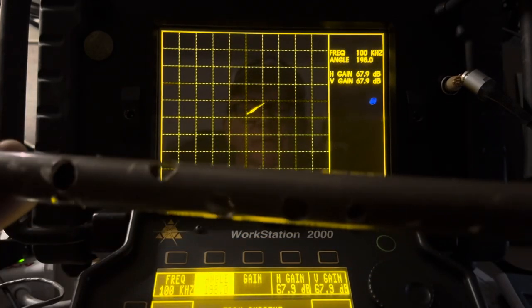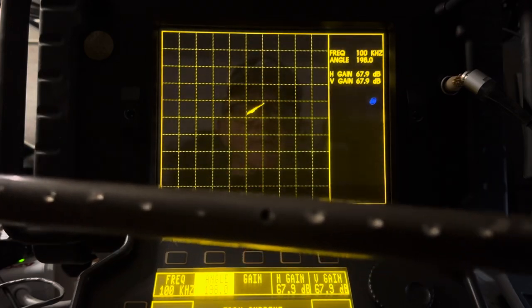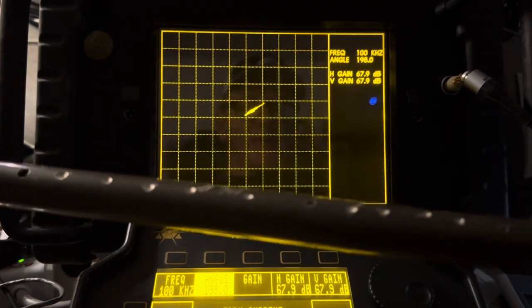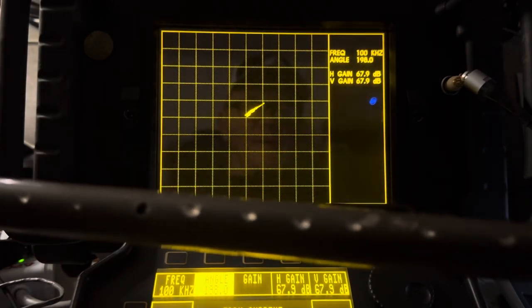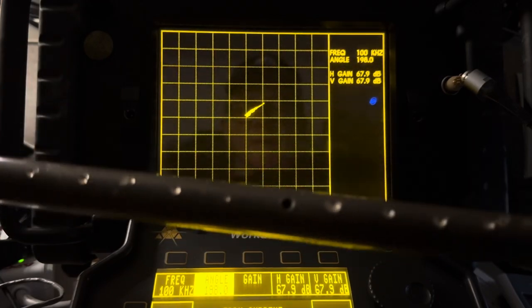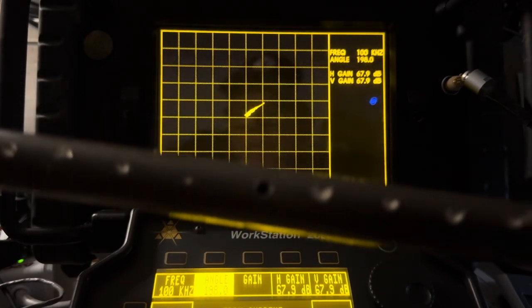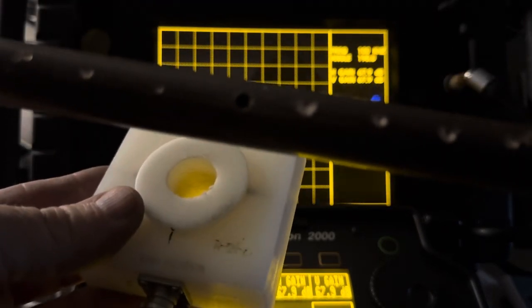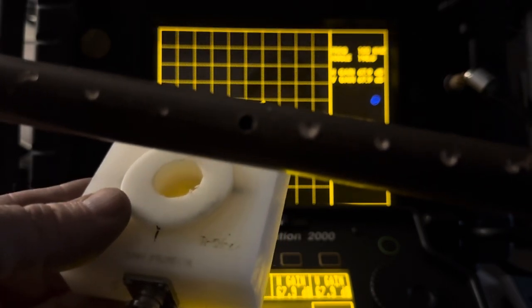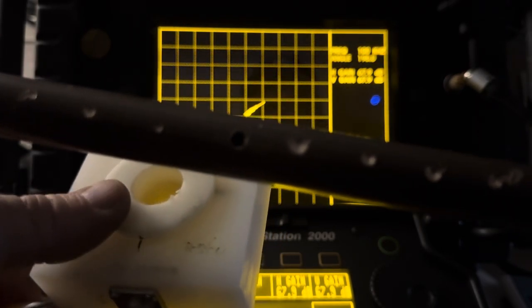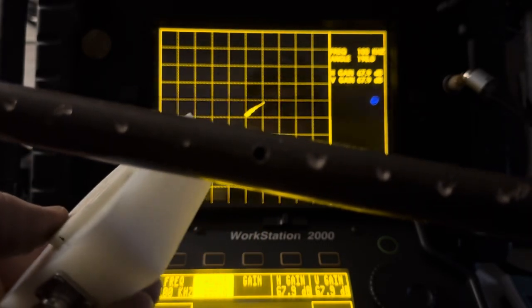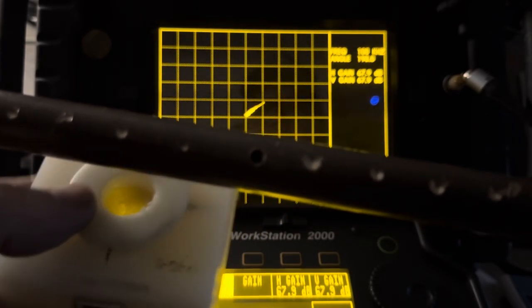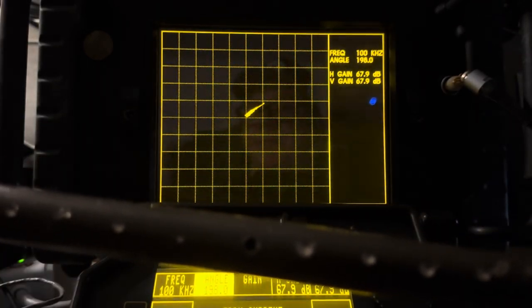This is an extreme example, but I have a bunch of wide flat bottom holes in this calibration standard. I had to use this particular cal tube because my encircling coil is quite wide, and a wide coil isn't very sensitive to very small discontinuities. So a 0.052 inch hole isn't readily detectable with a wide coil like this. I had to use something with bigger flaws.